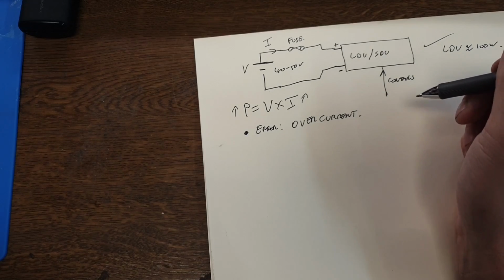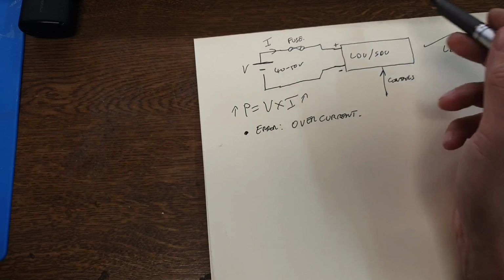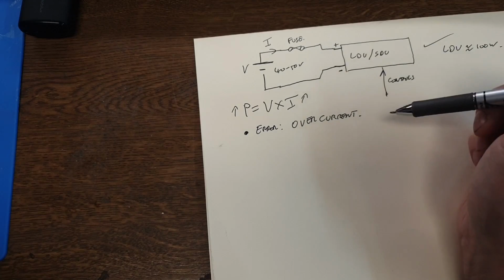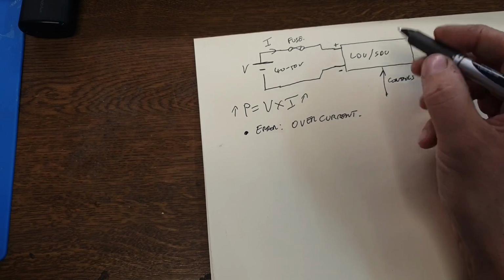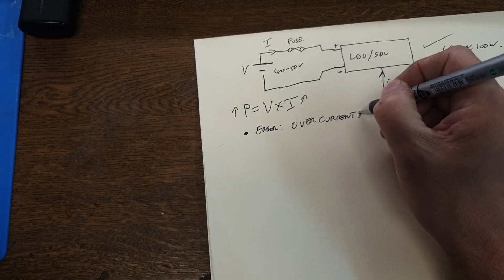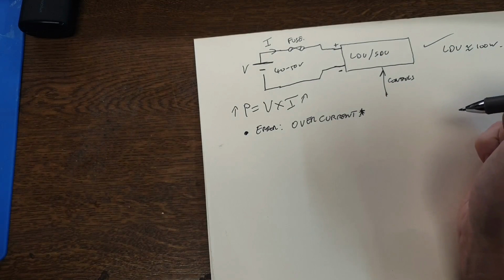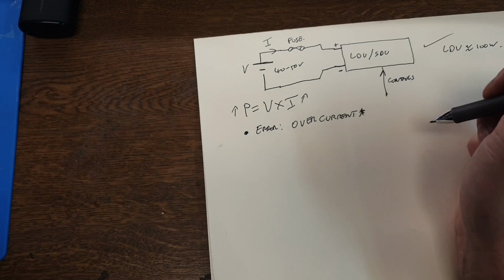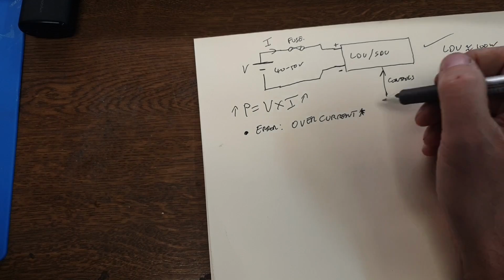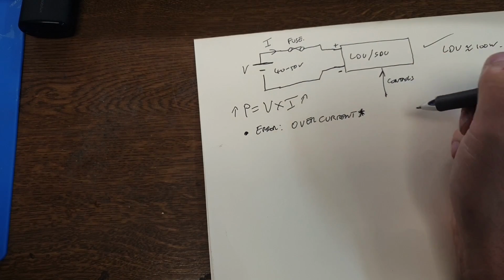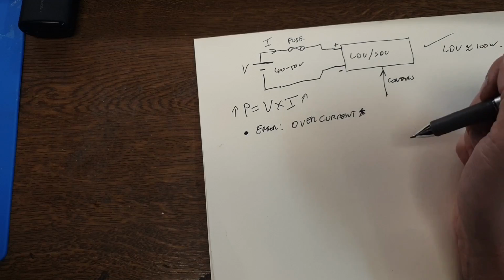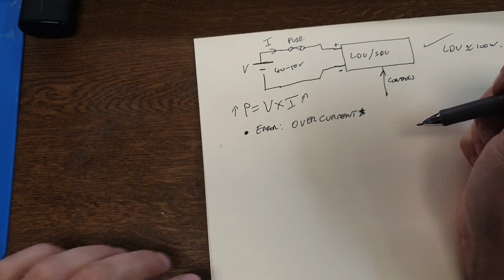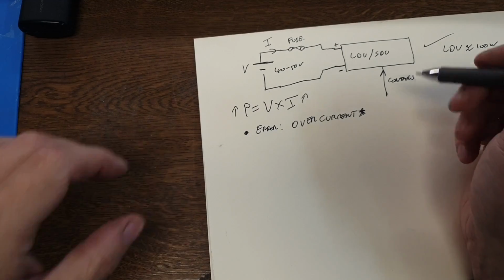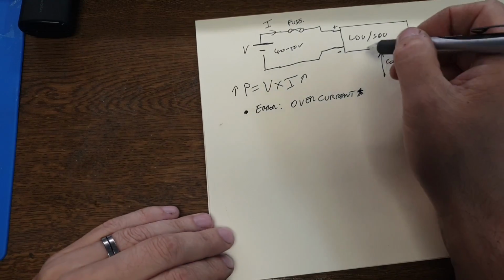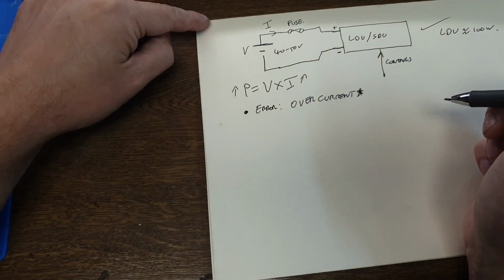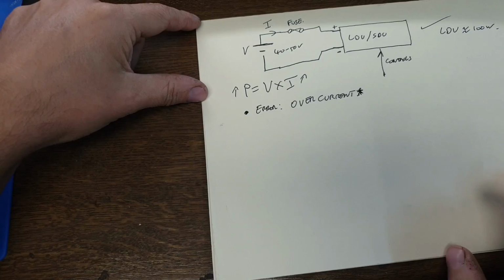Then we'll get a bit more confused and start changing settings and wiring and all this. But no matter what we do, this overcurrent error is going to persist and prevent the drive unit from turning. Now, the reason this has occurred is not because there's any actual overcurrent—it's because one part of the inverter has actually failed, and those are the power transistors.